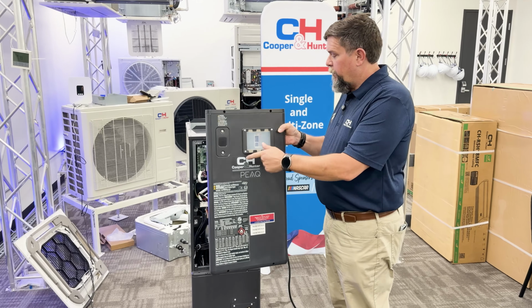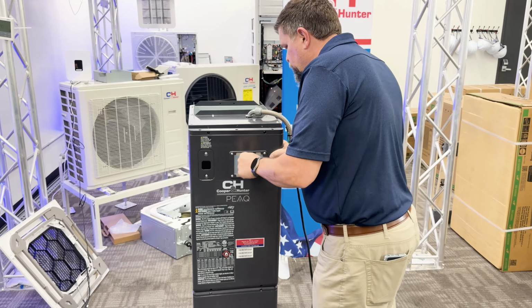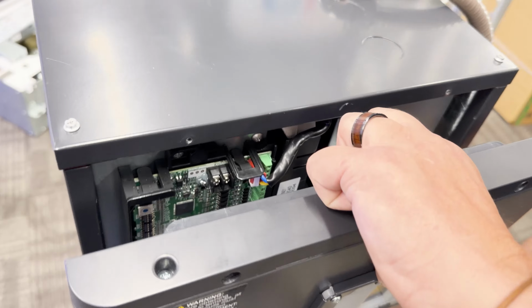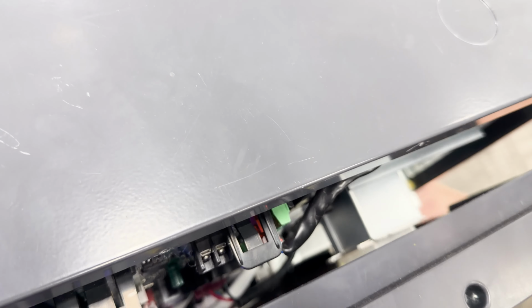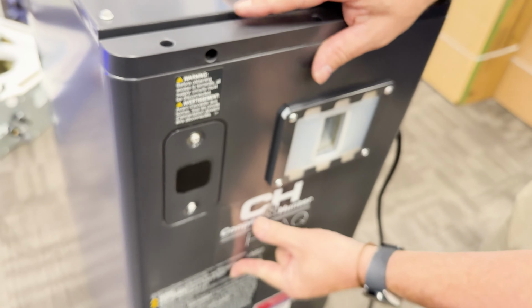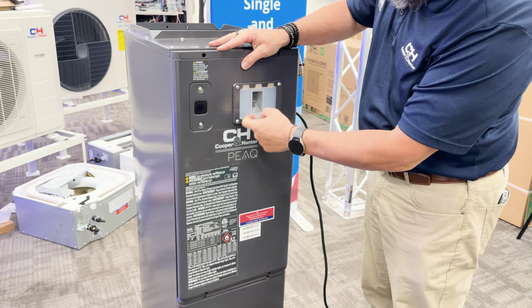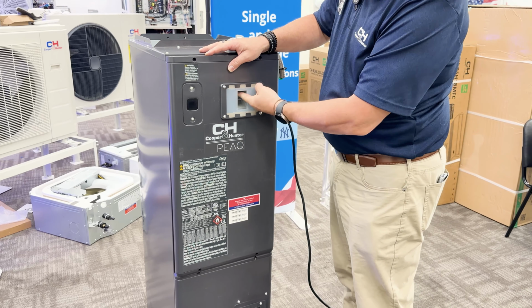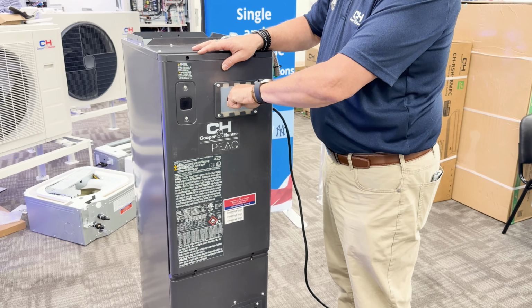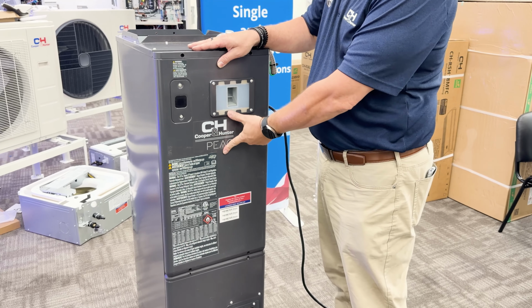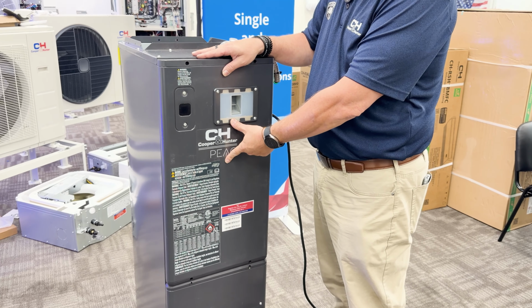With the silicone cover in place, now we can close the door. The silicone will line up with the bracket and covers the circuit breaker. Then put the screws back in the door. With the silicone in place, now we can safely turn on and off the circuit breaker for the auxiliary heat before we take off the door for servicing the unit.